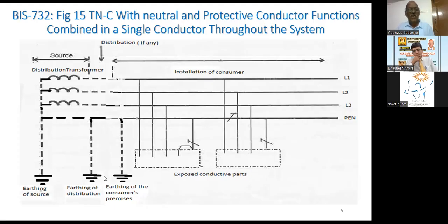Because of these combined earth resistance values, with several hundreds of consumers downstream of the transformer and several kilometers of line downstream of the transformer, they all will be constituting a combined earth resistance value, which will be very low if it is done as per CEA regulation. That's why the TNC system is adopted worldwide and in our country also.